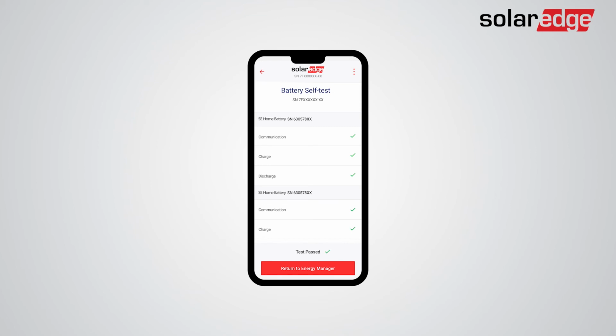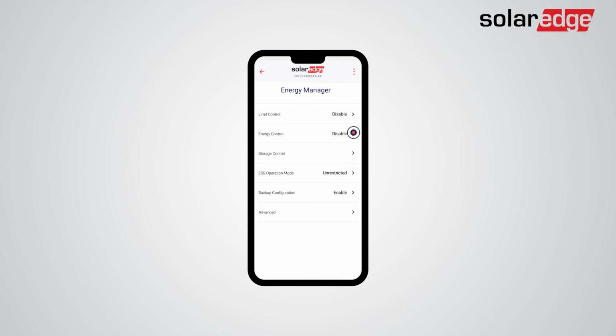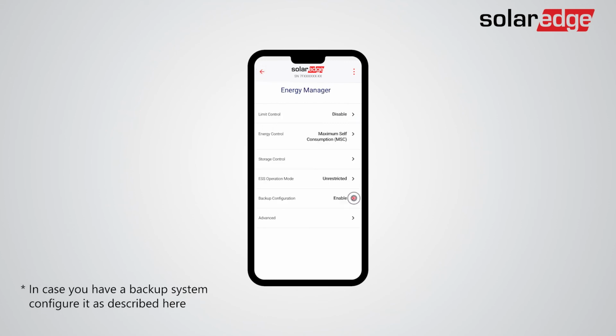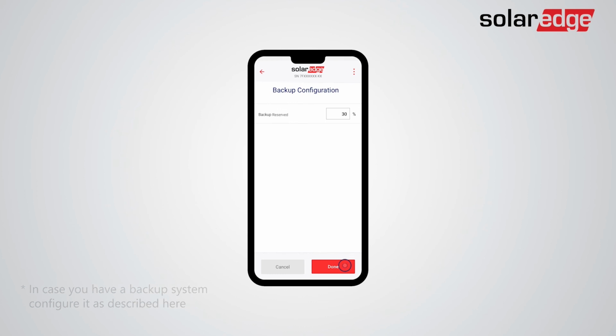Once the test is done successfully, you may return to the Energy Manager settings of the battery and conduct the various required settings. The next step is setting the energy control mode. Let's set it to Maximize Self-Consumption. Tap Backup Configuration. Now, we verify backup is enabled. Then, adjust your backup reserve settings.